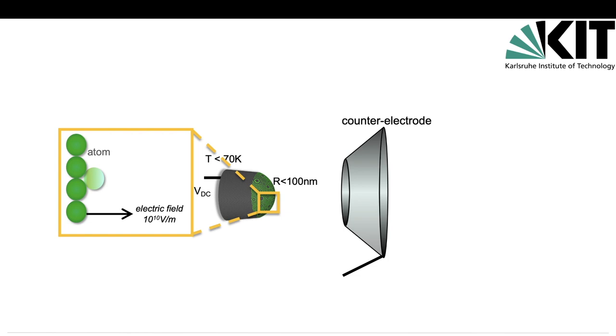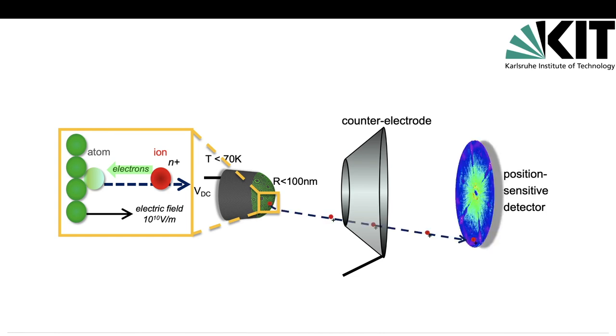Because of this huge electric field, the electrons in the surface atoms get drained and are finally moved into the metal itself, converting the atom into an ion. This process is called field evaporation, and this ion now gets repelled towards a position-sensitive detector on which the XY positions are recorded of the impact of the ion.